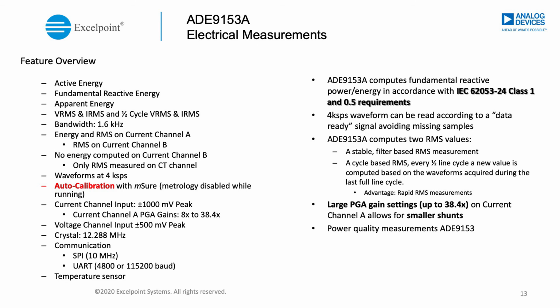The measurement bandwidth is 1.6 kHz. On current channel A, you can have energy and RMS value, while on current channel B you can only have RMS value—no energy will be computed on current channel B, only RMS measured on the current transformer channel. Then we can have a 4K SPS waveform.